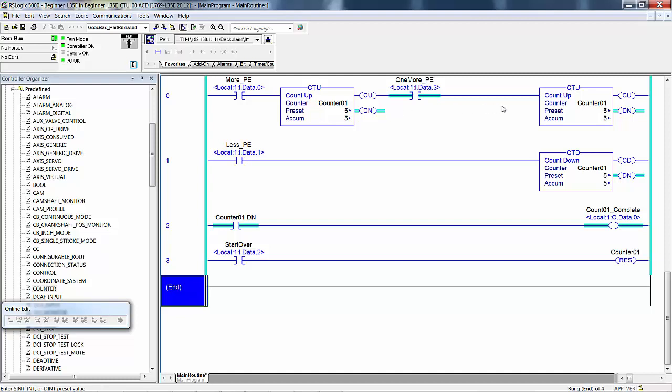At the end of the rung, this counter data type, counter 1, still only saw one false to true transition. Remember that both these instructions are addressing that counter data type. So if both of them basically simultaneously send a CU bit, count up, well, the data type's only going to count up once. It doesn't matter how many count up instructions you have in this rung like this.